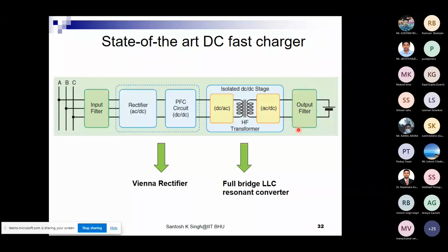Now, the state-of-the-art DC fast chargers have a higher power rating. At this power level, it is considered that we cannot use bidirectional converters, because the power level is quite large. The moment we start feeding power back into the distribution network, there may be a situation like overvoltage and protection tripping. So at that power level, it is assumed that a Vienna rectifier can be a better solution.